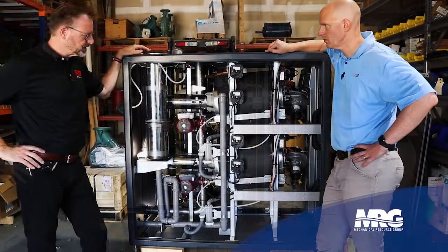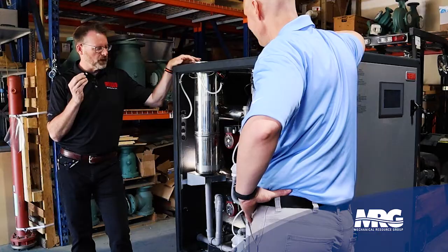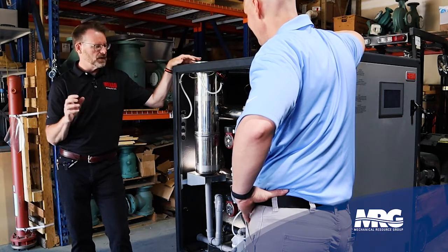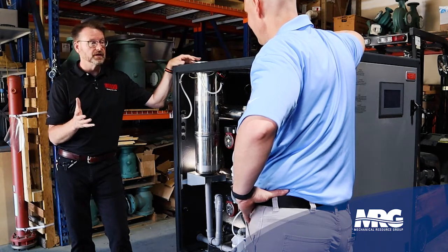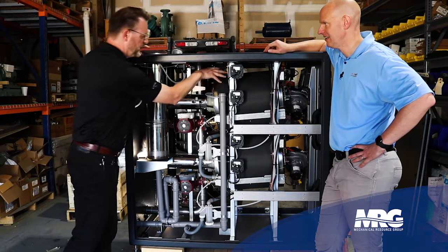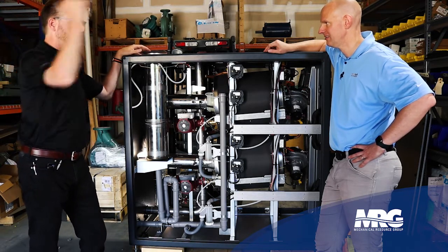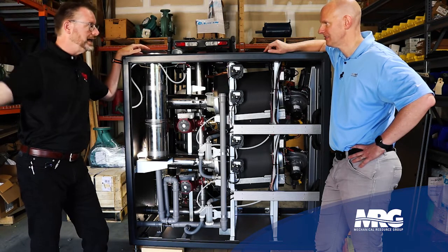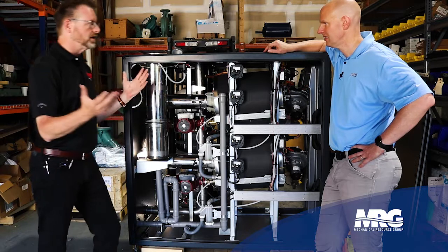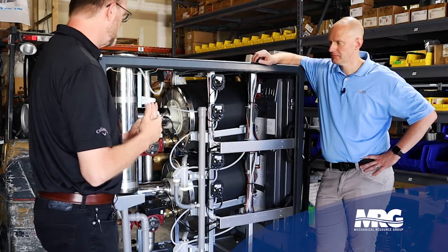Airlocked, yes. Gotcha. We talked to Tommy and Kevin about failures that they had and how they had addressed them. One of the failures that we weren't able to address from the front of the appliance was a circulation failure. The fired heat exchangers have got to have a method to move the energy from the fired heat exchanger to the system where the energy is desired, out in the building or in the pool or the hot tub or the hot shower, whatever it is. That energy doesn't travel wirelessly, it travels via the water, and the water's got to get pumped. That circulation is very important.